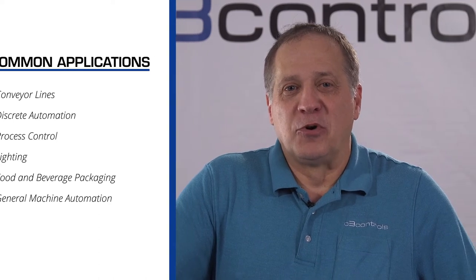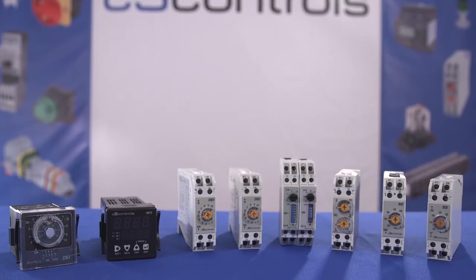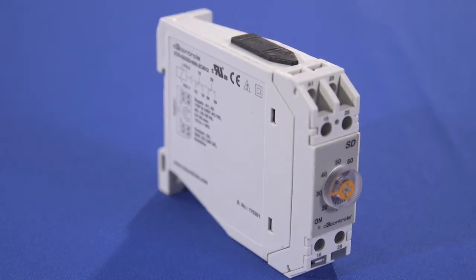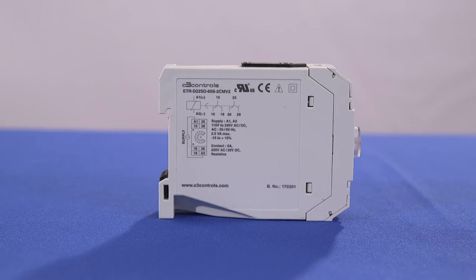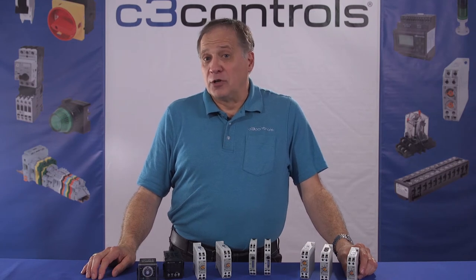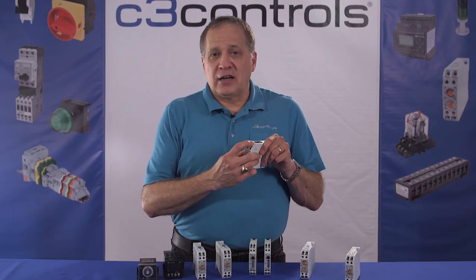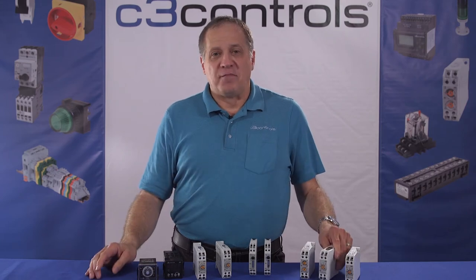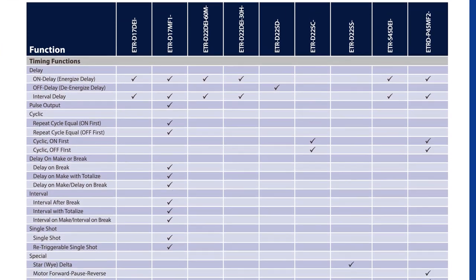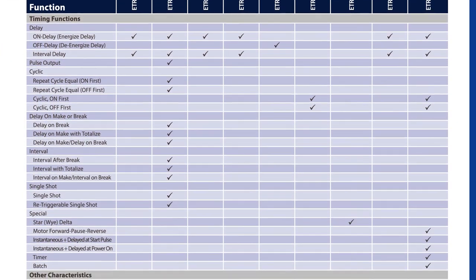What are the most important things to consider before buying an electronic timing relay for your application? Make sure to choose relays that are CE and UL listed, as you can use them anywhere in the world. Electrical ratings and product certifications are usually on the housing for easy reference. The timing relay must have good accuracy to deliver accurate control performance. IP20 guards protect against accidental contact with live parts. It is recommended that you select relays with multi-voltage capability, meaning they are capable of accepting a wide range of input supply voltages, which helps you reduce inventory.